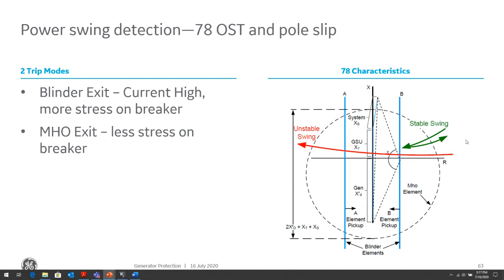So when we have a stable power swing, the locus will come into our Mho circle and maybe into our right blinder, but then it will exit back to get to a stable condition. But when it's an unstable condition, it will swing from the load point on the right through the Mho circle, through the right blinder, through the left blinder, and out the Mho circle. So we can tell the difference between a stable power swing and an unstable power swing by looking at that locus and the time that the locus moves through the Mho circle and those two blinder settings.